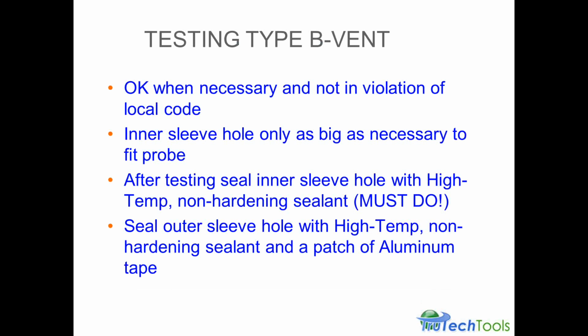In some situations you may need to test on B-type vent or type B vent, and this is okay when it's necessary and it's not in violation of the local code or the authority having jurisdiction. The basic parameters to follow are that the inner sleeve hole only be as big as necessary to fit the probe of your combustion analyzer, and that after testing you do actually seal the inner sleeve hole with a high temperature non-hardening sealant. This is a must: seal the inner, and also seal the outer hole with the same high temperature sealant and a patch of aluminum tape.